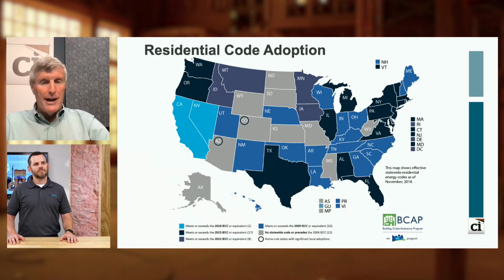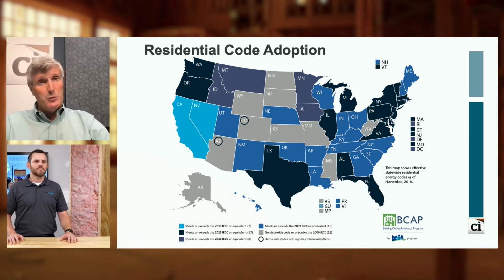But just want to go back to a few of those and mention to you, many on this call will already be doing air tightness testing of their buildings. Why is that? Because 28, I think it's 28 now, it's probably 30 now, U.S. states now require blower door testing of all buildings, air duct sealing or duct testing and air barrier testing. And why is that? Partly from an energy perspective, partly because of chances of problems for condensation within wall cavities, which we'll come to. So it's now a code requirement in many states.